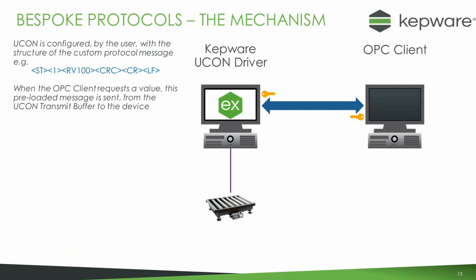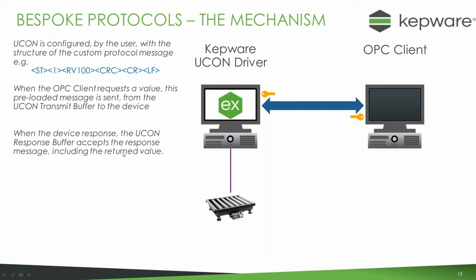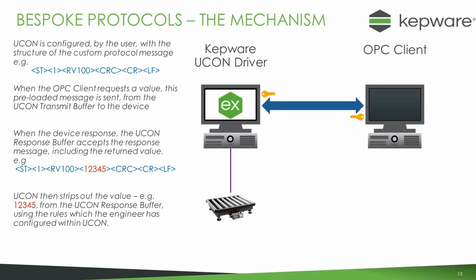When the OPC client requests a value, that message structure is sent via UCON's transmission buffer to the device. When the device responds, the UCON response buffer accepts the response. A typical response might include the value 12345. Within UCON, you set rules to locate that value in the response string, strip it out, and pass it back to the OPC client. So you create custom rules for sending the message and custom rules for extracting the response value.